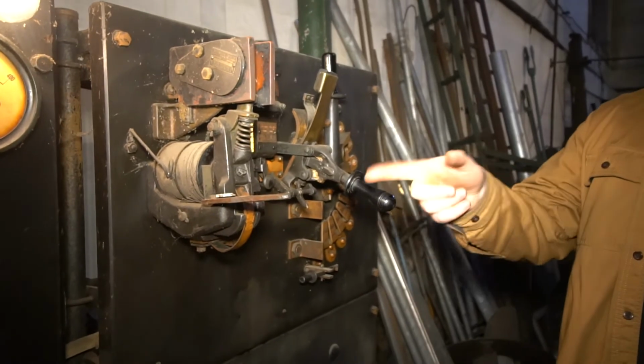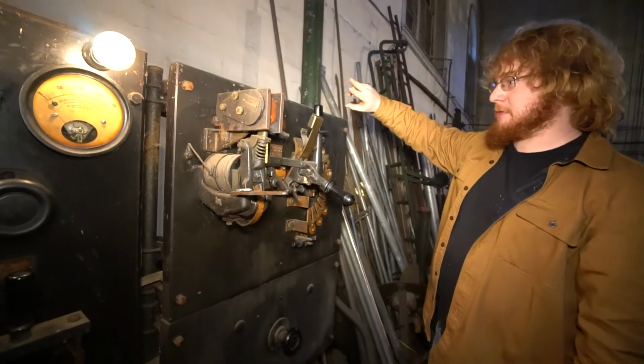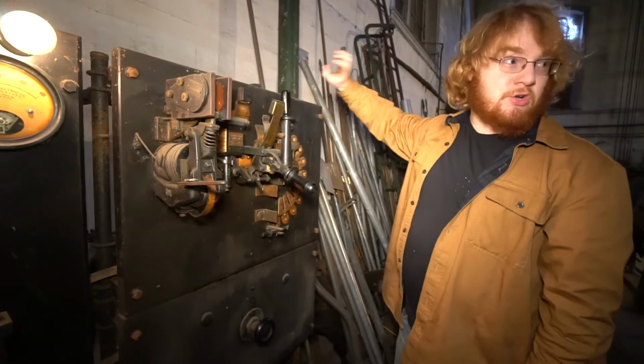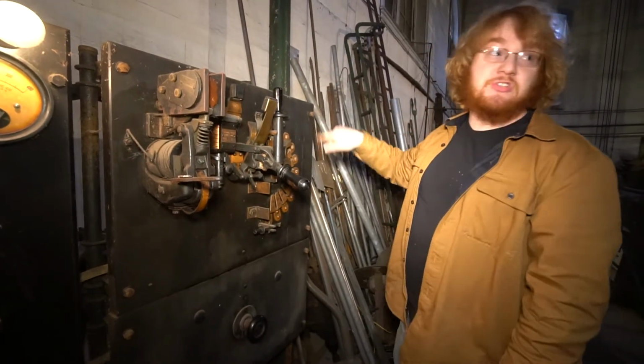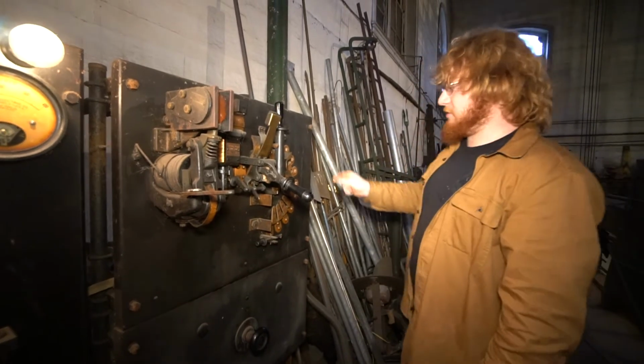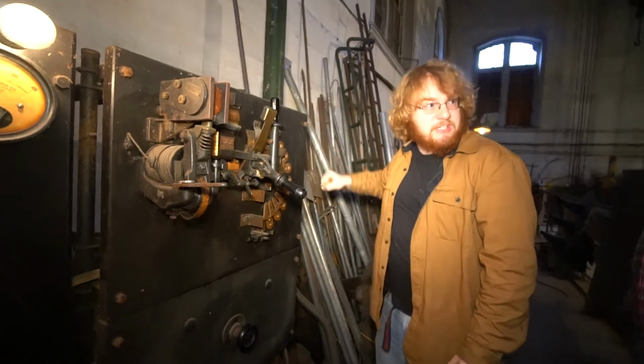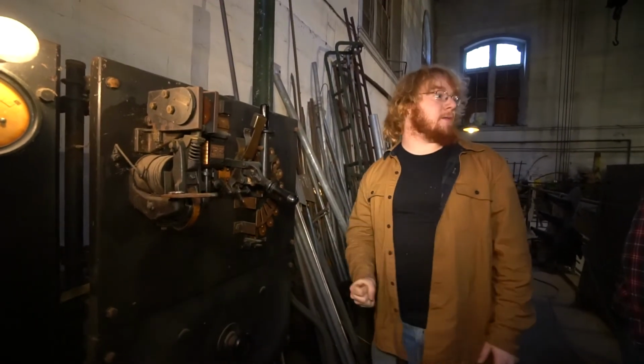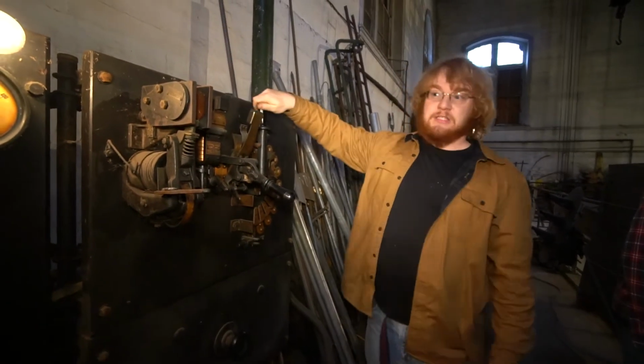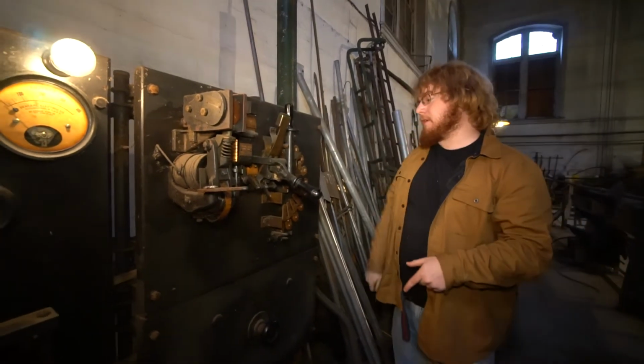This contactor, we won't talk about that. There's actually a dead man system in this, so when you're starting this motor, this is a soft starter, basically, so you're not starting it all the way to power at once. This goes through a series of resistors, which allows the voltage to come up slowly, and your speed to come up slowly. And you, as the operator, are running it, both watching the machine and the ammeter.